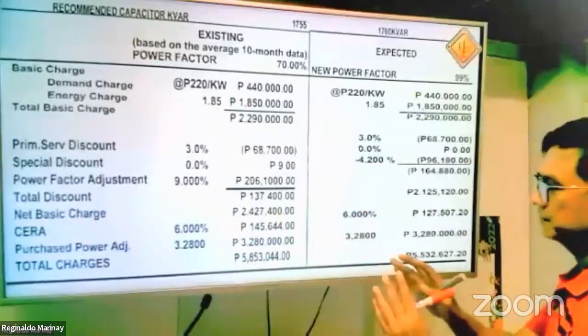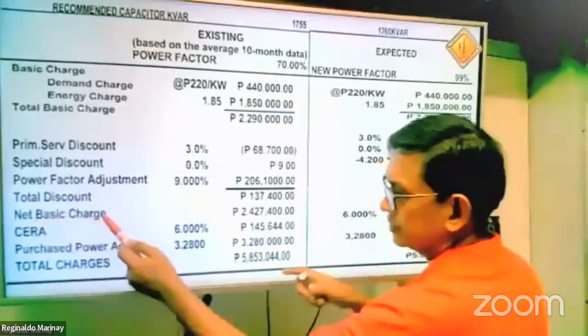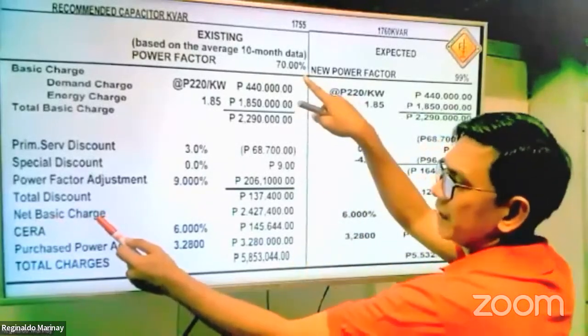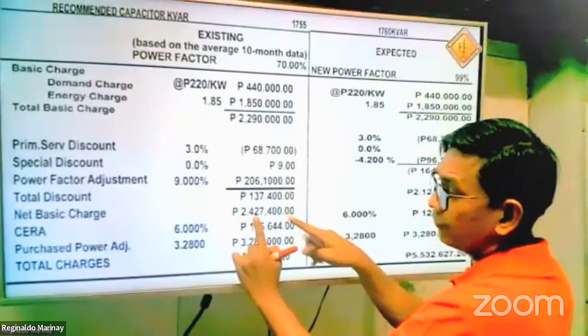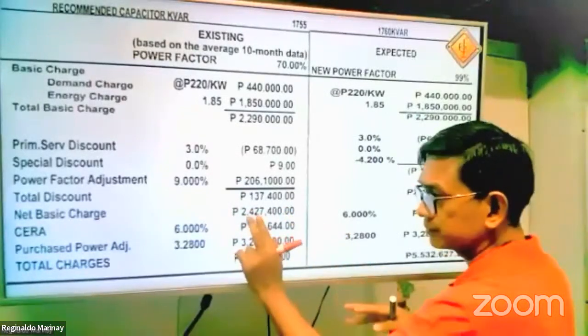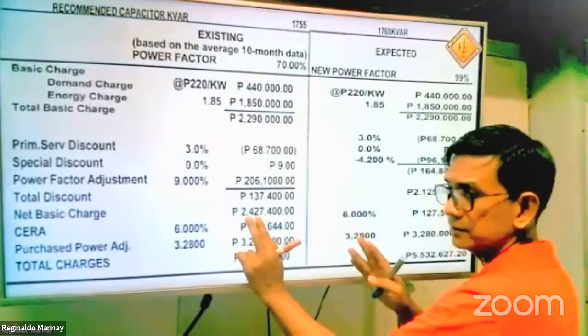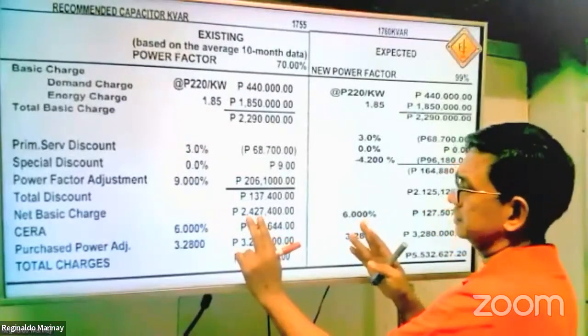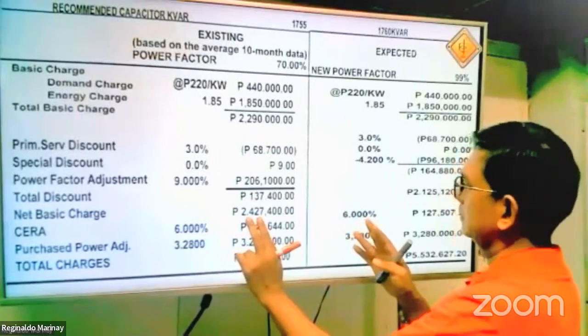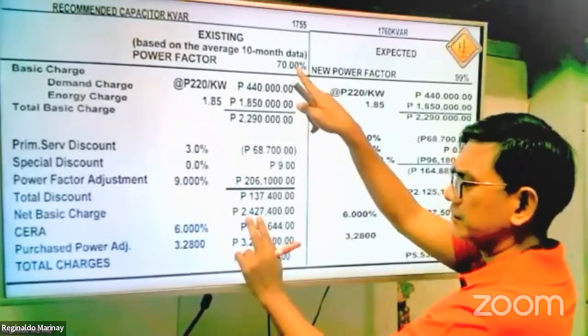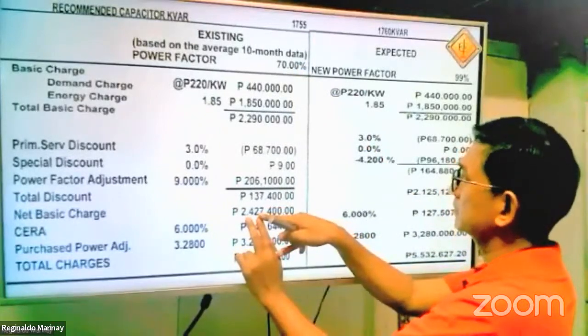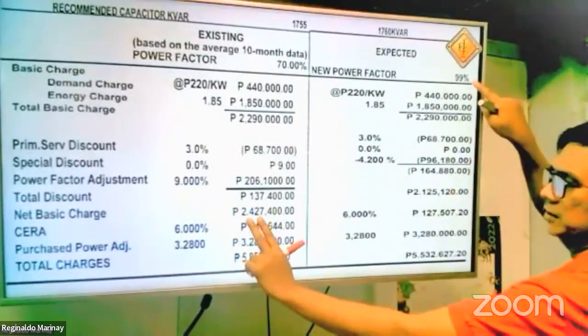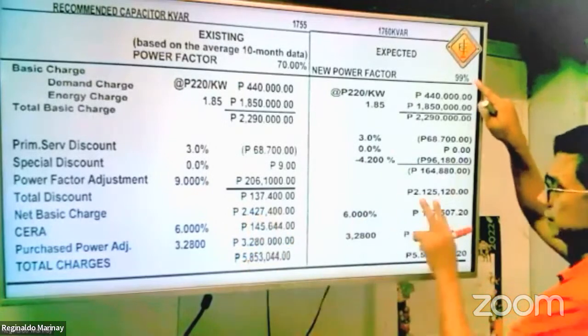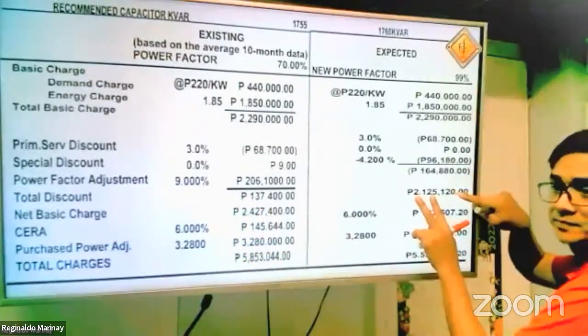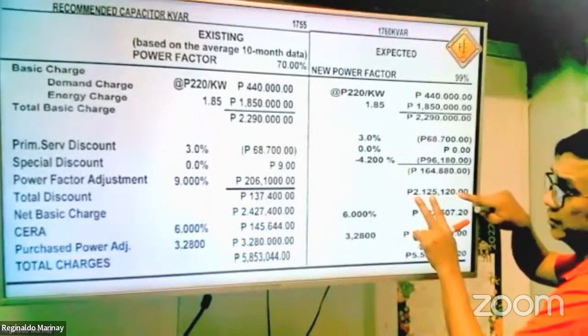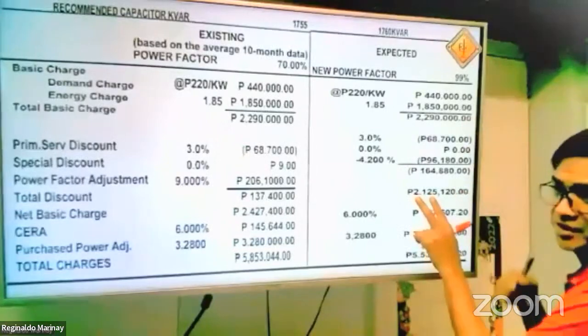Now let us stop here. The net basic charge, if you have 70% power factor, is around 2.427 million, rounded off. That is the net basic charge for 70% power factor. For 99% power factor, the net basic charge is 2.125 million, which is lower than at 70%.